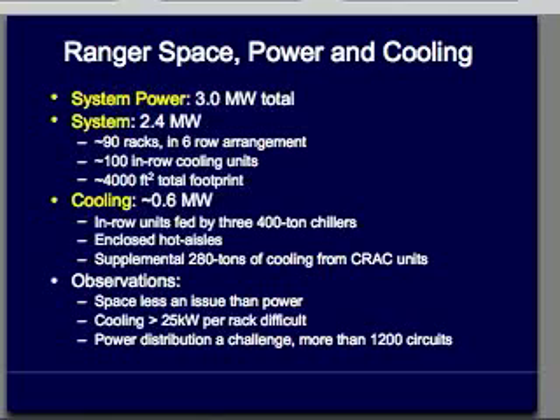Just some observations here: multi-core is really making space less of an issue, but unfortunately it's making power a disastrous issue that we all have to face. We had to have a design which would cool greater than 25 kilowatts per rack, and that's why we're using these in-row cooling units. One of the challenges was power distribution, because the racks are still being driven by 240 power, so we had to deliver more than 1,200 circuits to the 82 compute racks in our machine room.